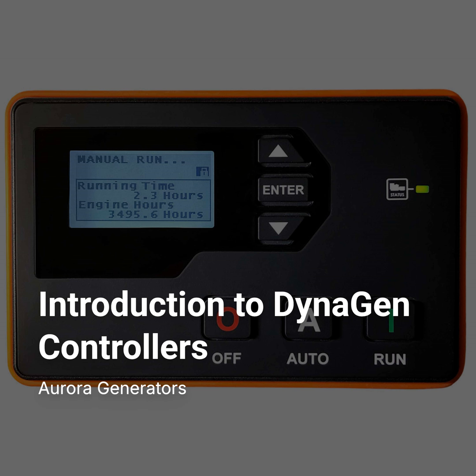relay expansion modules. Okay. What about installing them in challenging environments, say places with a lot of electrical noise or maybe exposed to the elements? They offer some practical advice there too. For noisy environments that might interfere with speed sensor signals, they recommend using twisted pair cables for the sensor wiring, run directly to the controller. Twisted pair, right. Helps cancel out noise. Precisely. And using isolated two-terminal sensors with twisted pair is also good practice for minimizing interference.